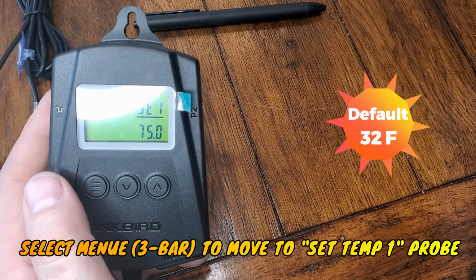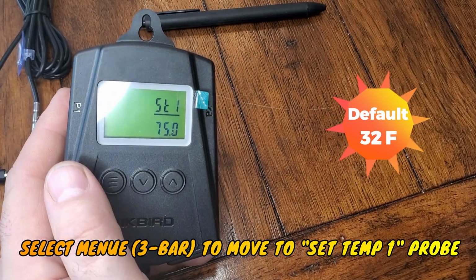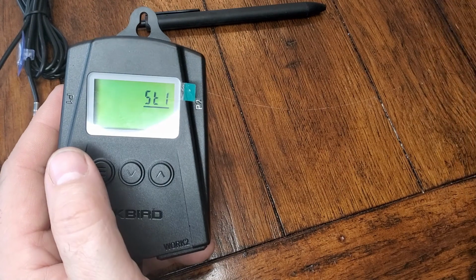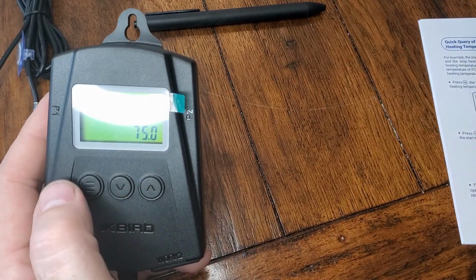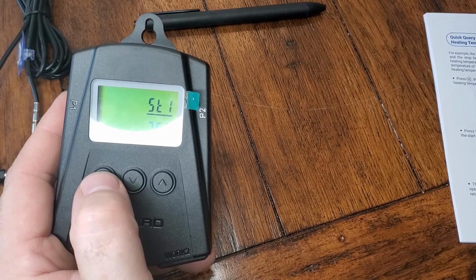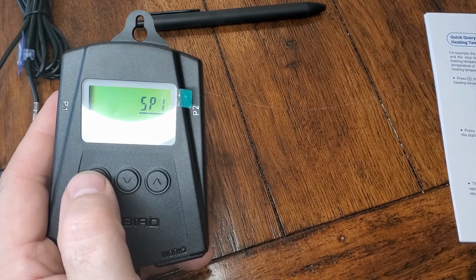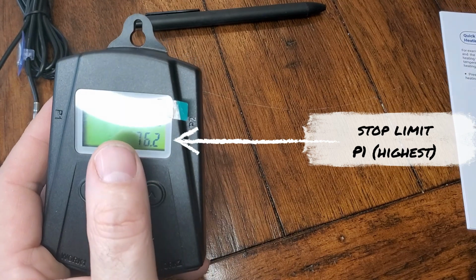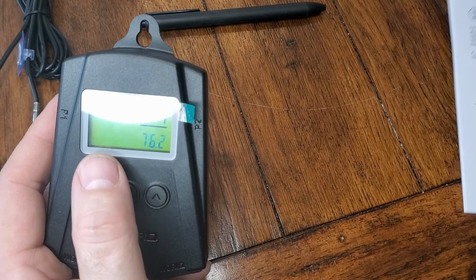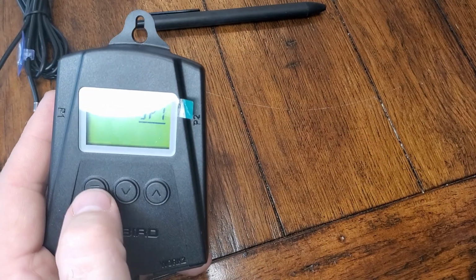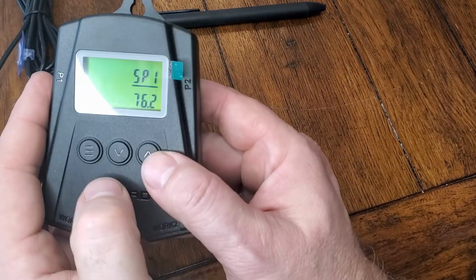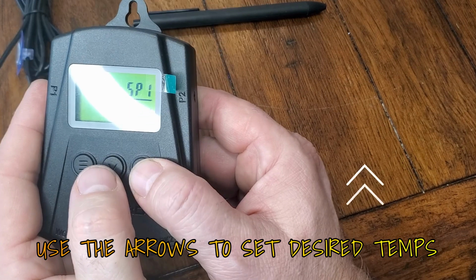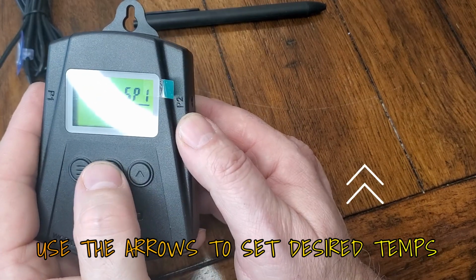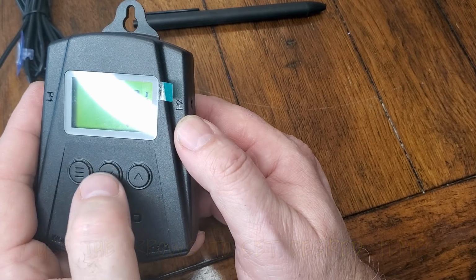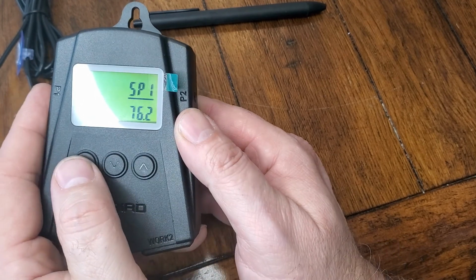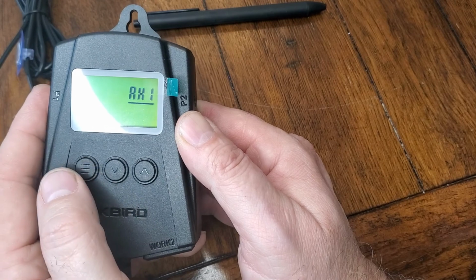And that moves me on to my set temp 1. So ST1, and then I set that for 75 degrees. Now I'm going to hit it again. And it's going to basically show my high limit, SP1, 76.2, is what I set this for. Now if I want to change this, I can use my arrows. I can go up or I can bring it back down. And let's put it back at 76.2. Now I'm going to hit it again.